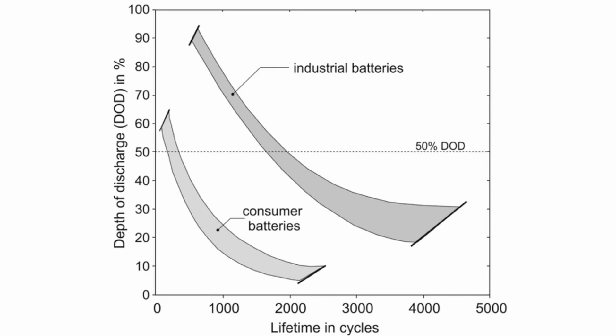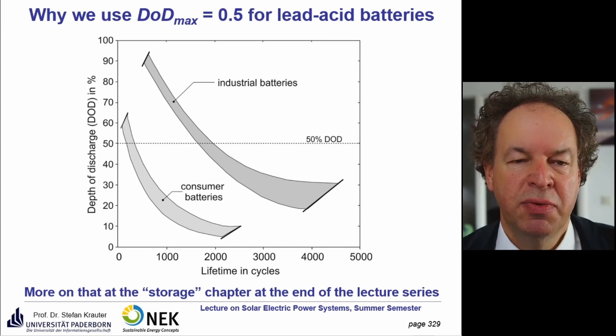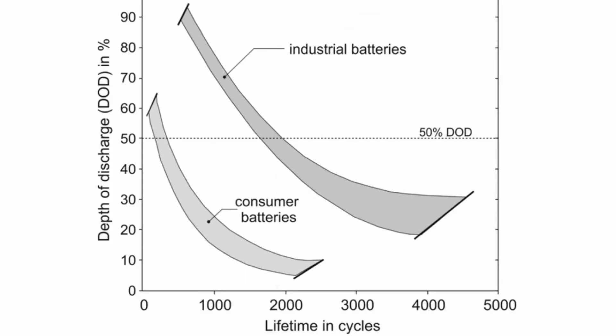Battery lifetime depends on brand and especially temperature. A rule of thumb: increasing battery temperature by 10°C halves the lifetime. This will be covered in the energy storage chapter. For this exercise, we take 50% depth of discharge, giving approximately 1,800–1,900 full cycles. Since we don't need full cycles every day, the actual lifetime is longer — estimated at about 10 years, corresponding to roughly 3,600 cycles.